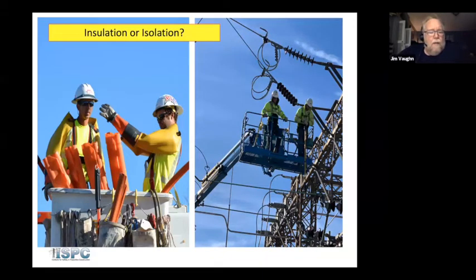So the first thing is that we have three ways that we can do work. Now, we can insulate, we can isolate, or we can work it as if it's dead and grounded. Now, with isolation, it's a little bit different than insulation. For instance, these guys over here on the left-hand side, they are insulating, and they're going to be putting cover up on the circuit to insulate conductors. They're wearing rubber goods, which also provides insulation, and their primary means of protection is their rubber goods. Now, we're not going to spend a lot of time talking about it, but the bucket that they're working out of for gloving is known as a Category B bucket, and even though it is isolated by an insulating boom that we test for integrity, the bucket itself is not considered your means of insulation. Your means of insulation are your rubber gloves, or if you're using hot sticks.